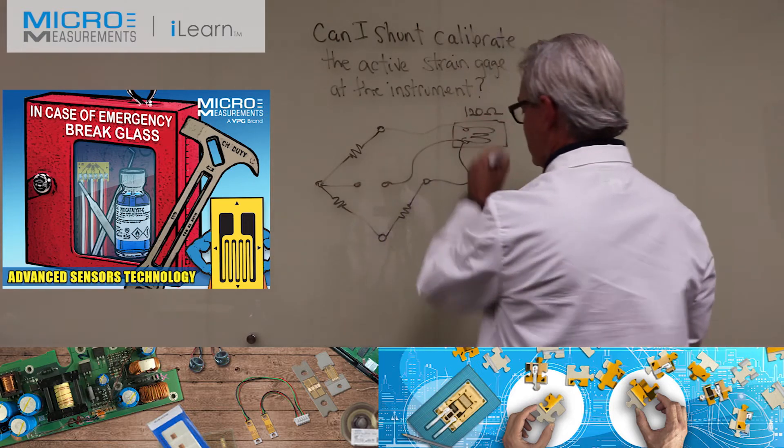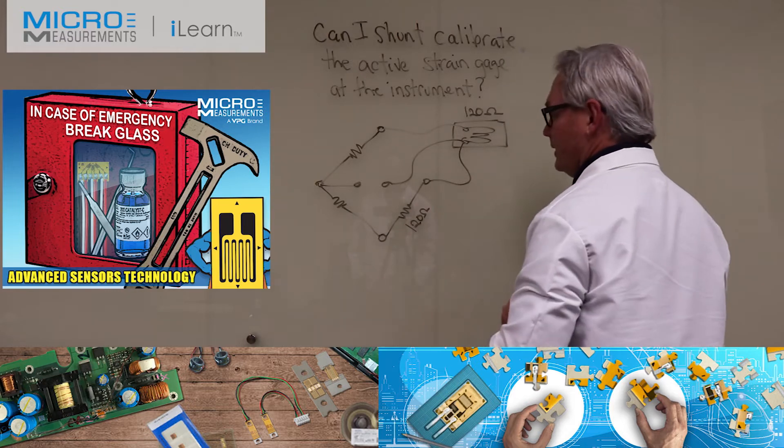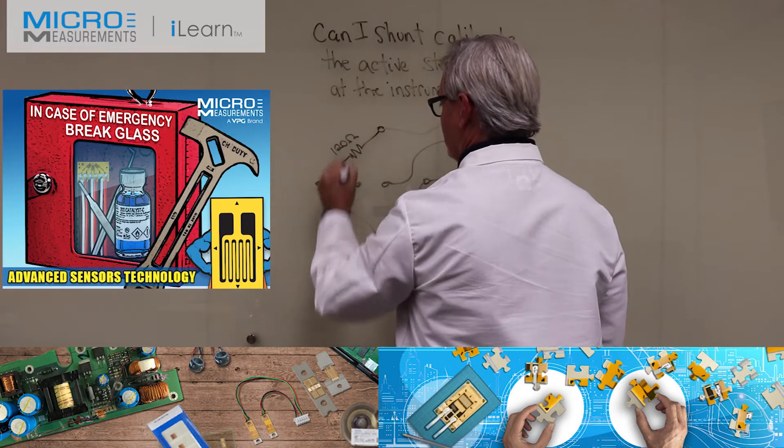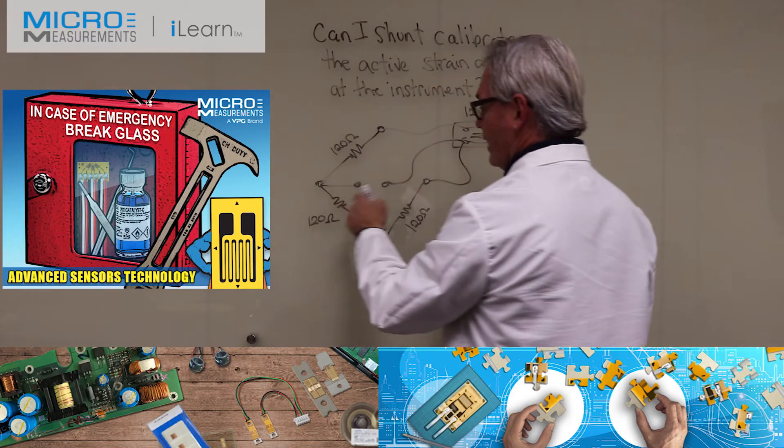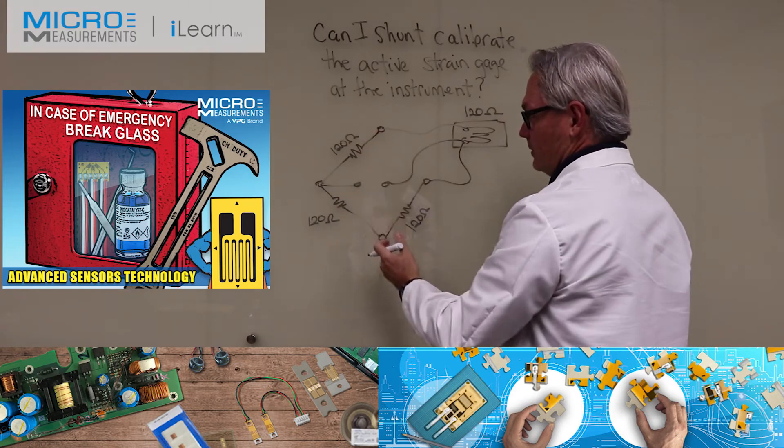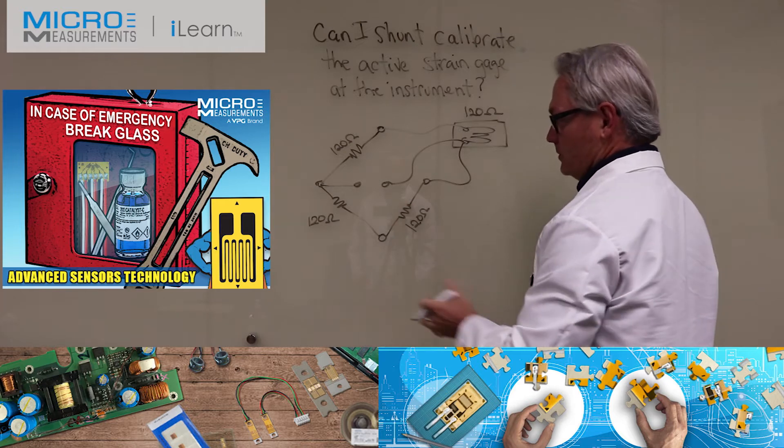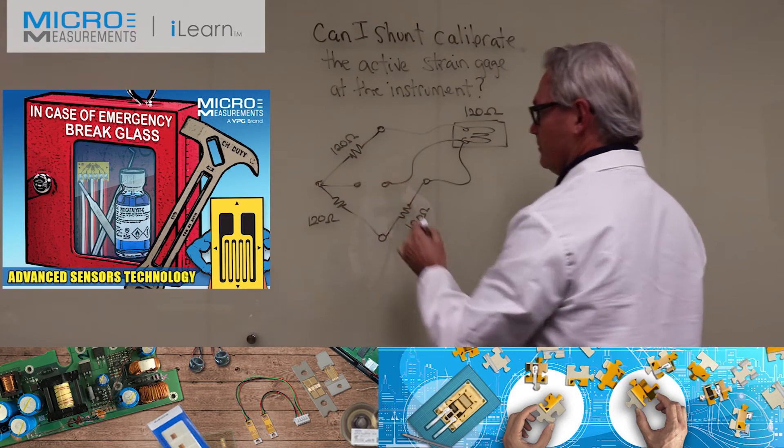If this strain gauge is 120 ohms, this resistor has to be 120. Let's assume that these are all 120 ohms. They don't have to be, but the internal half bridge could be 120, 350, or a thousand. Since they're on the other side of the bridge from the gauge and this dummy resistor, they could be any one of those values, but we'll assume for now they're 120.